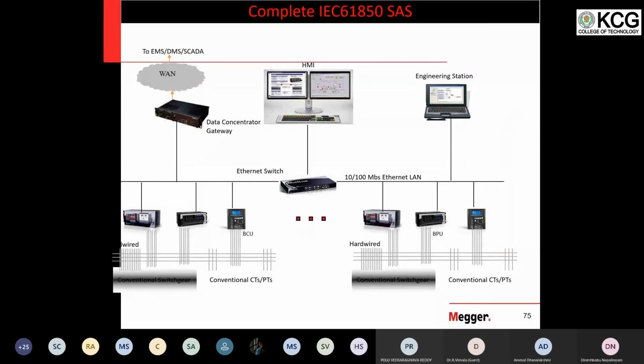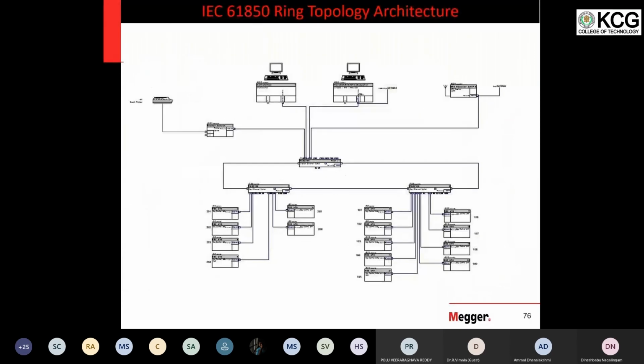Different types of architectures. Okay, so let me explain this architecture. We have different relays, an Ethernet switch, computers, printers, a SCADA system, and your time synchronization. So these are relays. Actually, 2 stands for 230 kV, 1 stands for 110 kV. So in our example, we had 4 230 kV incoming lines and 8 110 kV lines. So the incoming 230 kV line relays are here. 110 kV relays are here.